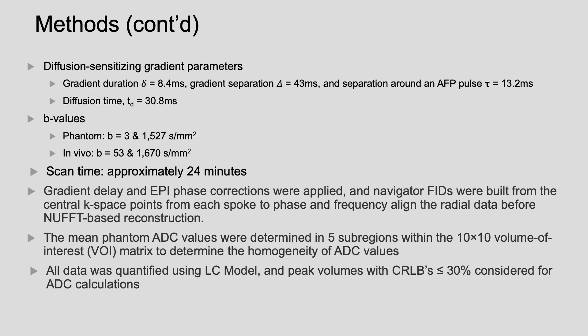All data was quantified with LCModel, and metabolite estimates with CRLBs of less than 30% were considered in the ADC calculations. This table shows the ADCs of 6 metabolites within the GE Braino phantom, and these were averaged across 5 different subregions, shown above, ranging from a 2 by 2 matrix to a 10 by 10. The results show that the ADCs measured corresponded well with the reference ADCs previously published, shown on the right column.